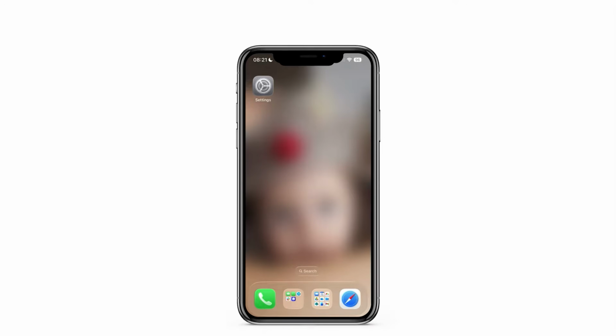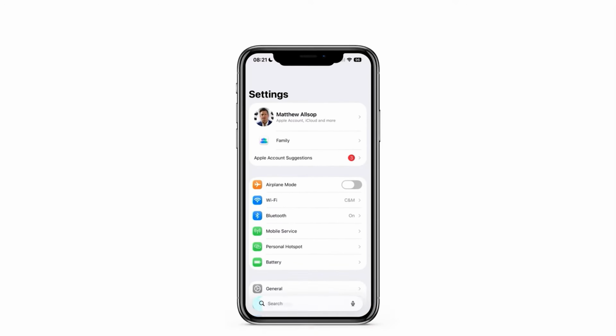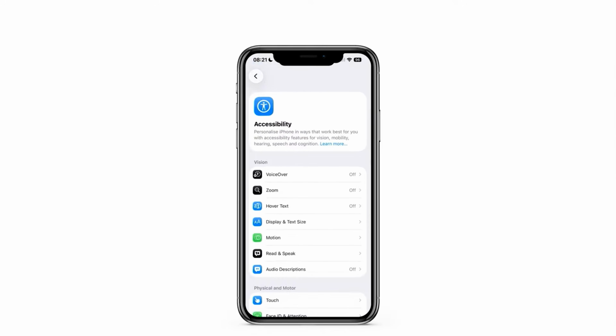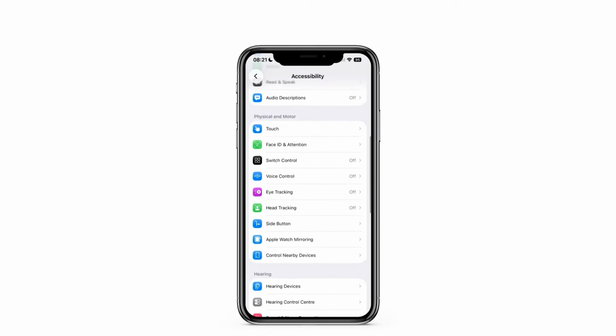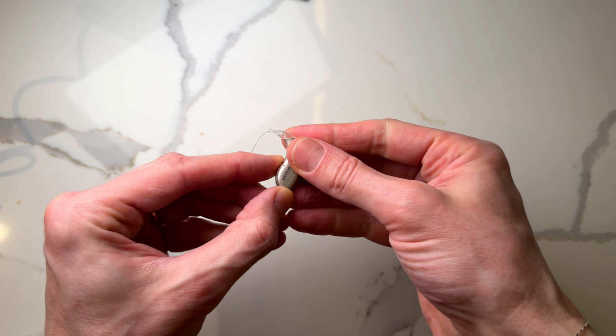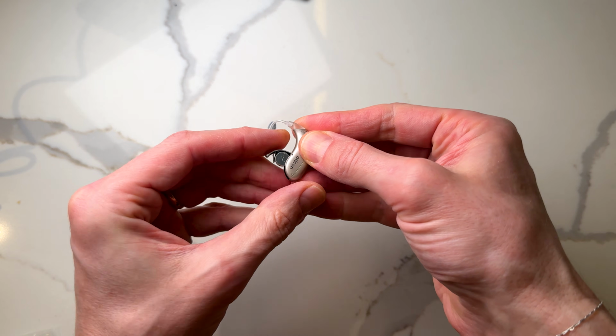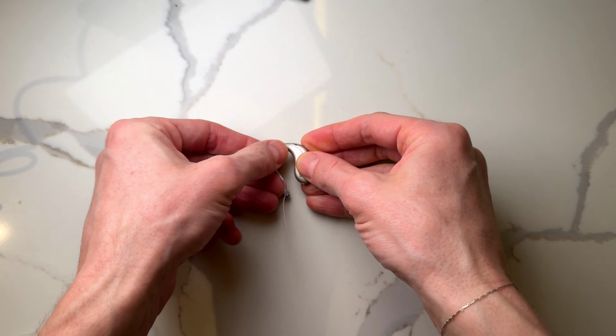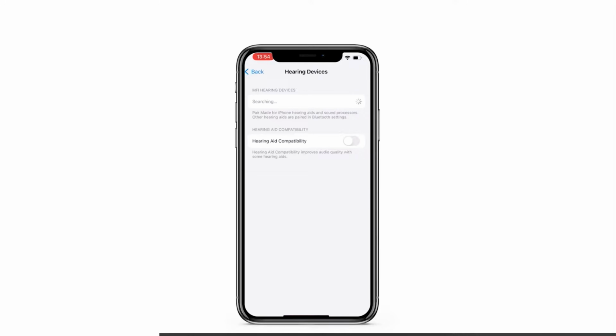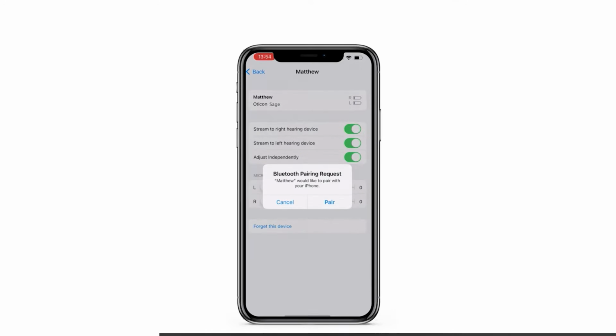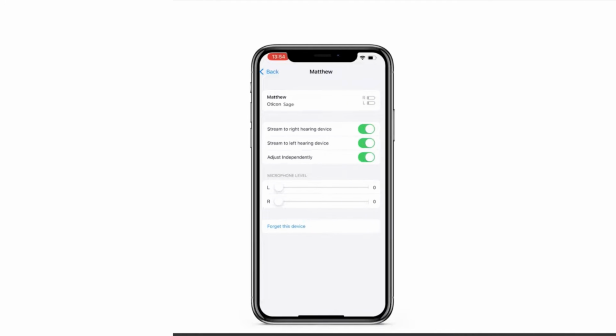To set this up, head over to the settings menu on your phone and scroll down to accessibility, then scroll down until you come across hearing devices. Next, open and close the battery door. This will turn them on and off and put them into a pairing mode for 60 seconds. Finally, at the top of your screen, your hearing aid should appear. When you press them, this will prompt you to pair, and then you're good to go. Once you're paired, head over to Google Play or the App Store and download the Oticon companion app to be able to make changes to the settings on your hearing aid using your phone.